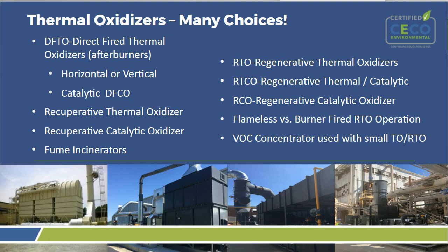There's flameless versus burner-fired RTO options. Most of these systems can be done. We've seen and have done RTOs ourselves in both electric heat and burner. And there's also catalytic units out there that operate electrically and also have burners. And typically, a lot of industries will call these fume incinerators. If you have especially high VOC concentration flow rates, concentrators are used there for high flow rates and low volumetric inlet loadings. And usually we'll put a small DFTO or small oxidizer or some type there. Typically you're going to see that in the paint industry, in composites, in several of those types of industries.